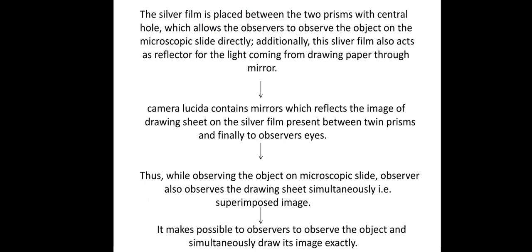The Camera Lucida contains two sets of prism arrangement. A silver foil is placed between the two prisms with a central hole, which allows the observer to observe the object on the microscopic slide directly. This silver foil also acts as a reflector for the light coming from the drawing paper through the mirror. The Camera Lucida contains a mirror which reflects the image of the drawing sheet onto the silver foil between the twin prisms and finally to the observer's eyes. Thus, while observing the object on the microscopic slide, the observer also observes the drawing sheet simultaneously, making it possible to draw its image exactly.